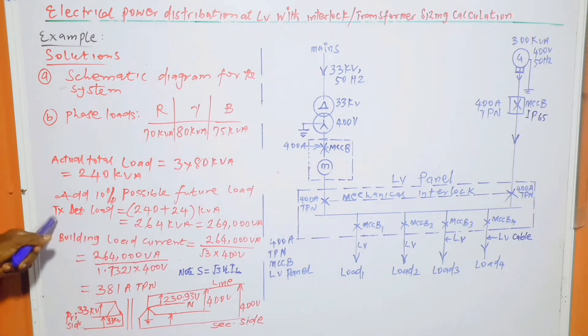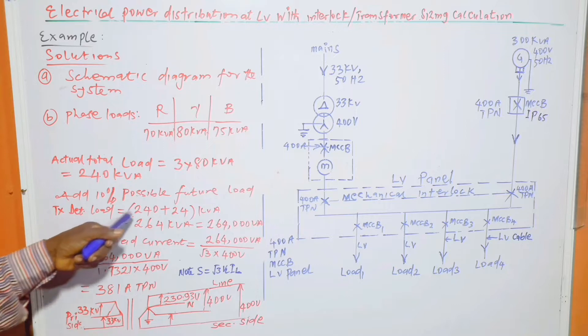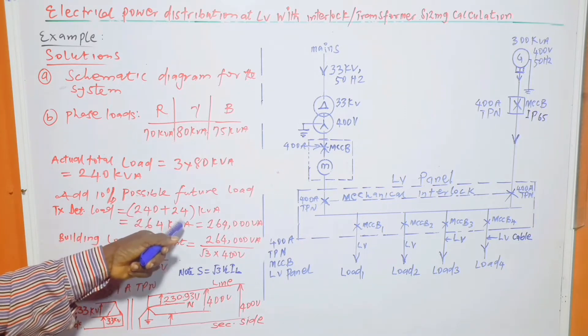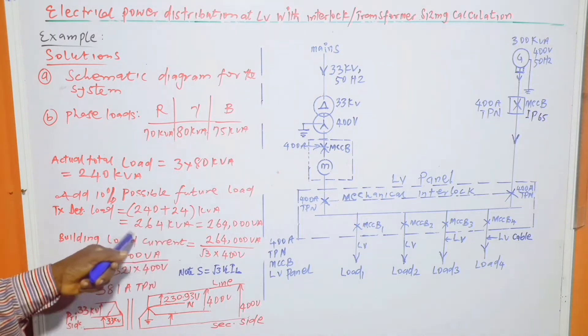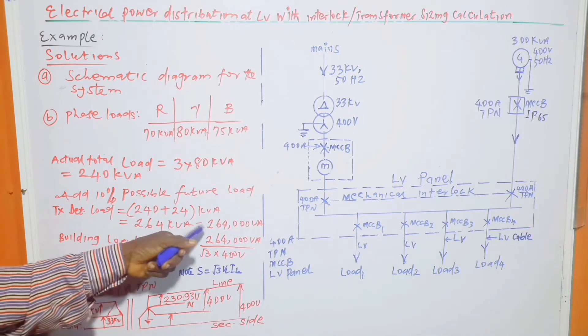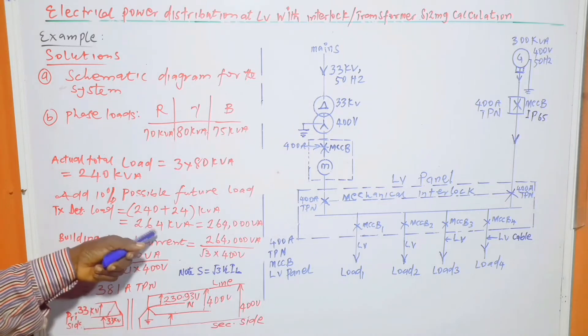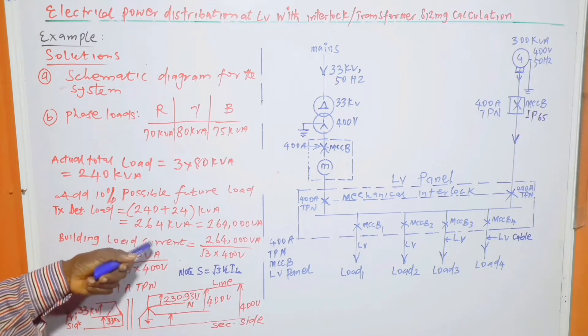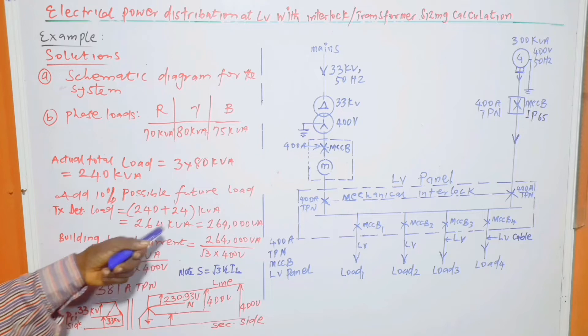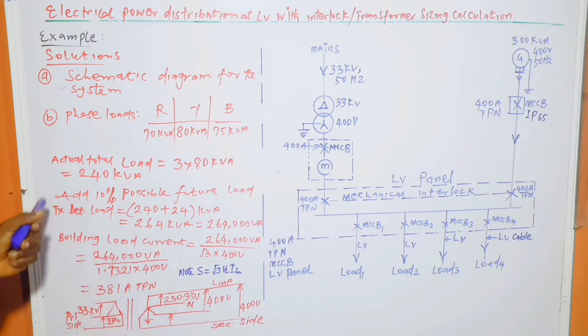Now, add 10% possible future load, then transformer rating determining load is equal to 240 plus 24 kVA, which is equal to 264 kVA or 264,000 VA. So this is the building load, 264 kVA, which is the answer to part B.